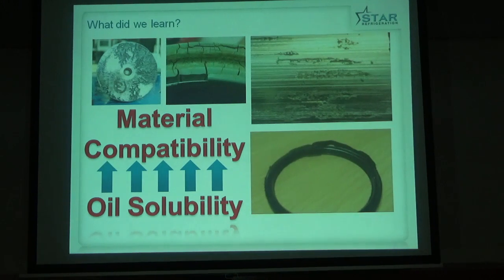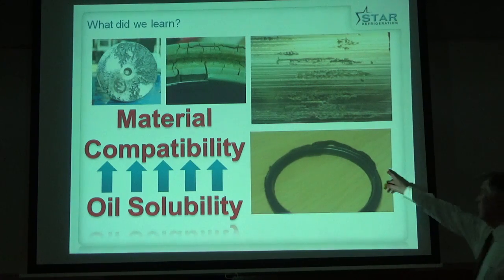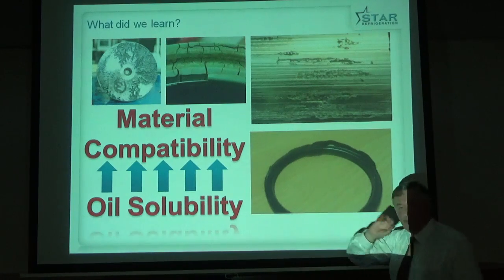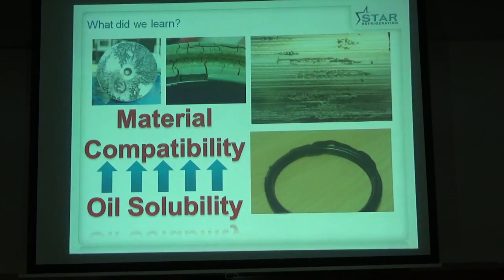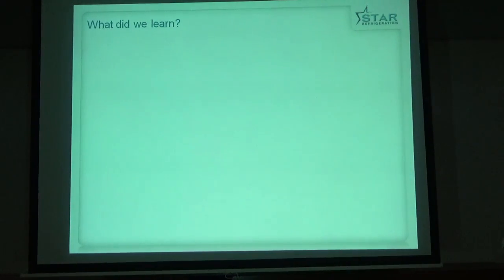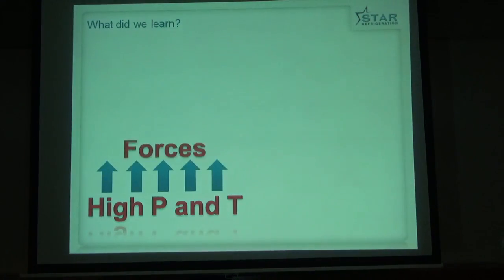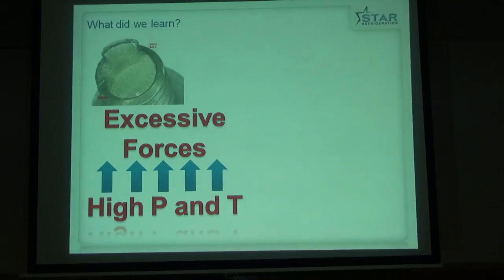And finally an O-ring, also available in a round cross section as this one originally was, but it's been so highly pressurized and squeezed that it's actually been extruding. This is a thin ribbon of O-ring material which has been squeezed between the two flanges because the temperature and pressure were so high. So high pressure and temperature give us excessive forces.